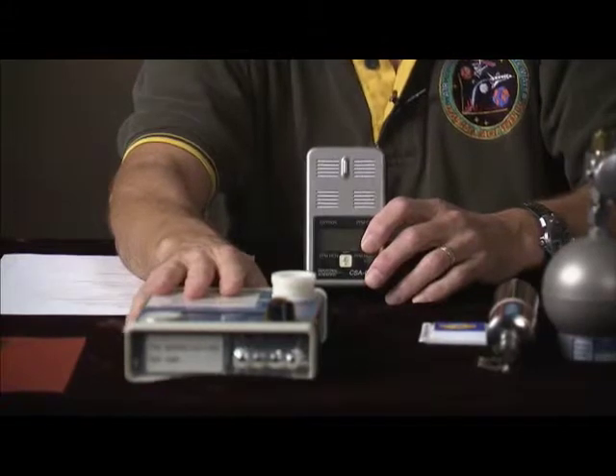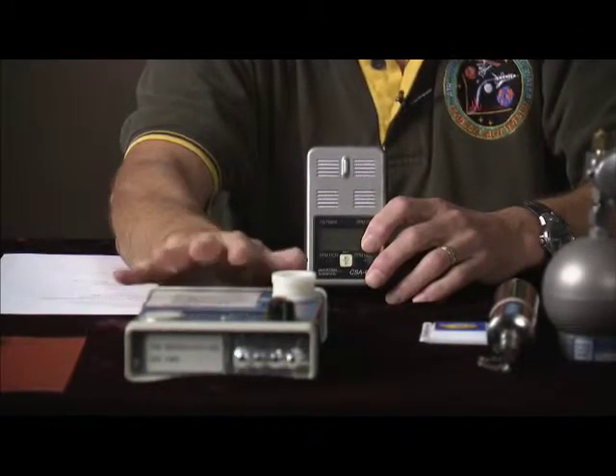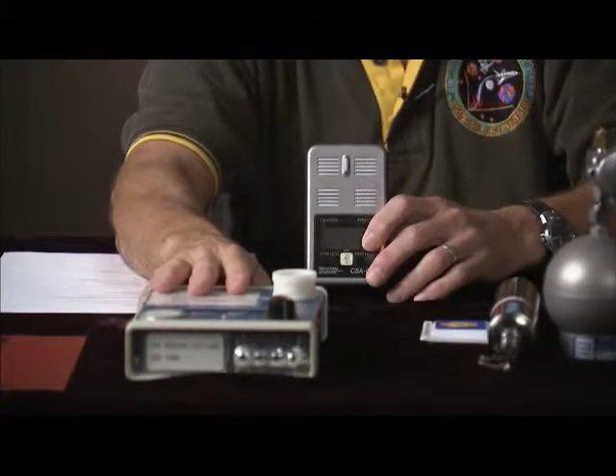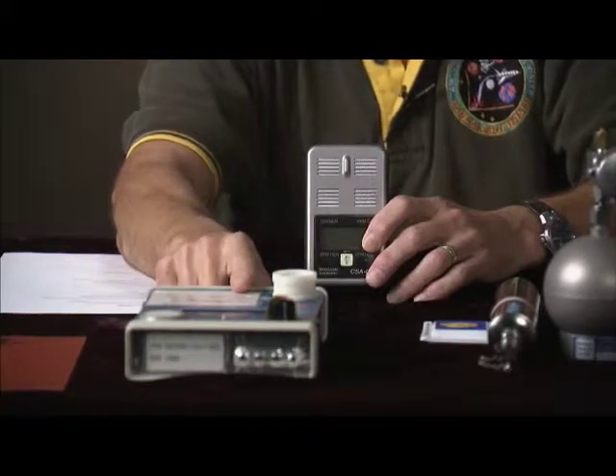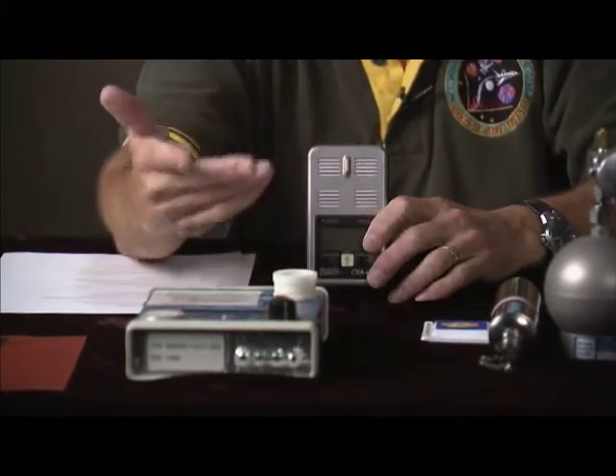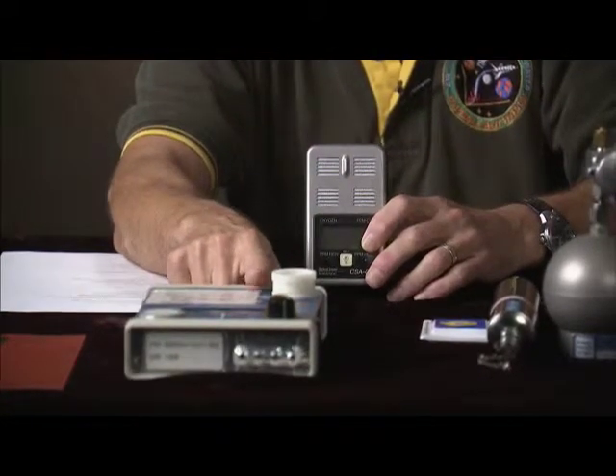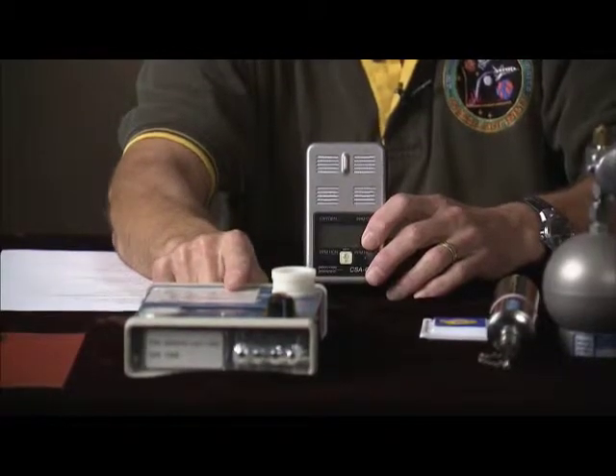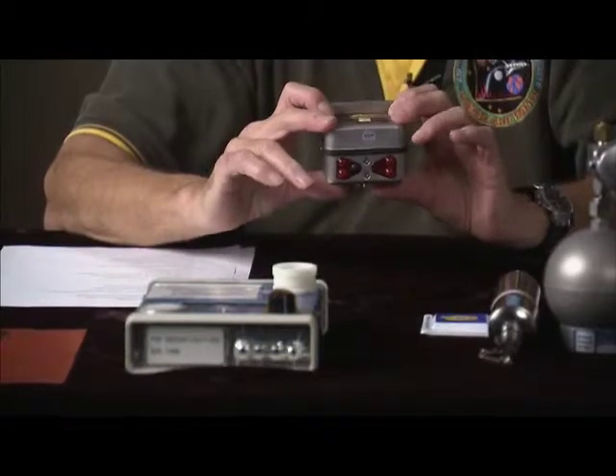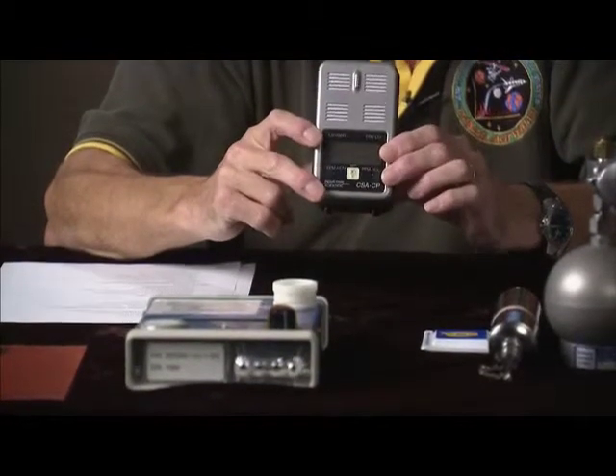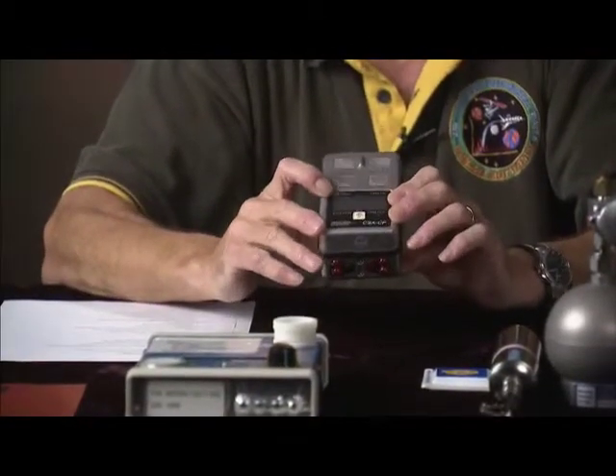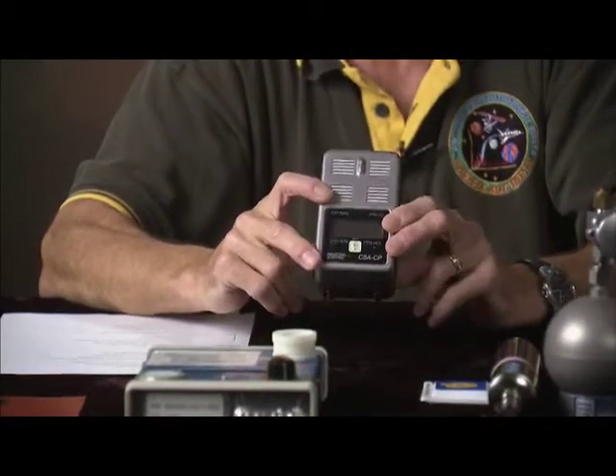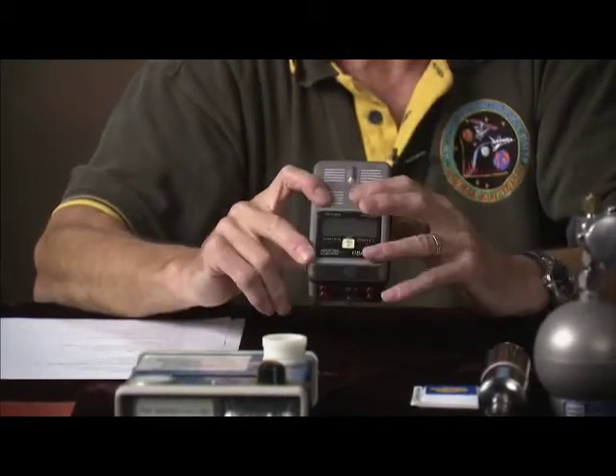The one failing we saw as chemists was that the hydrogen fluoride sensor never worked right. Hydrogen fluoride is important to monitor because it's a key product from wire insulation burning. We struggled to get a hydrogen fluoride sensor that would work, and we never did. We went to another instrument, shown here, a good bit smaller and much lighter, but there's still no hydrogen fluoride sensor available for these units.